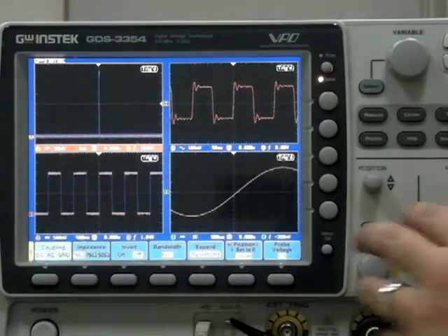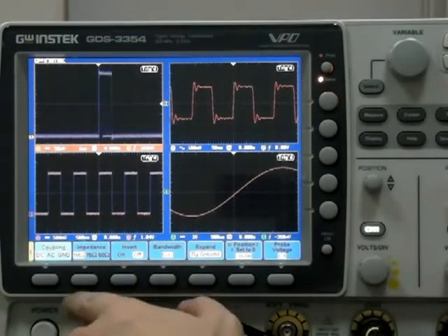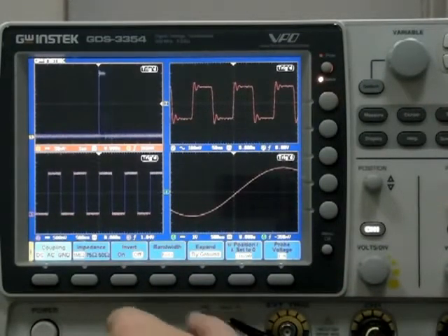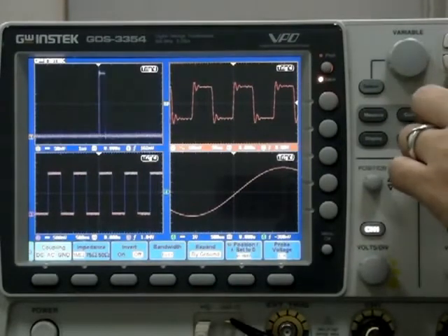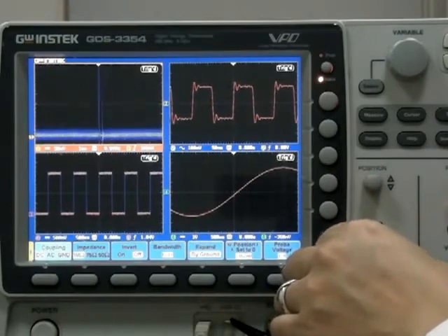Press the channel 1 to channel 4 key to set the impedance. 1 MΩ, 75 Ω, and 50 Ω for each channel independently. This allows you to match the impedances of different applications. This is just like using multiple DSOs together to perform measurements, making it an indispensable aid.